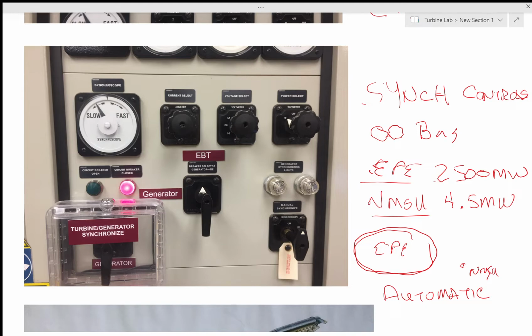You can also do it manually — that's what these two lights are for. One light is on the El Paso Electric system, and one is hooked up to our turbine. When you're in sync, those lights will be nice and bright. So you can go over and either hit the EBT breaker close right here, or we also have a generator breaker switch outside, and close it manually.